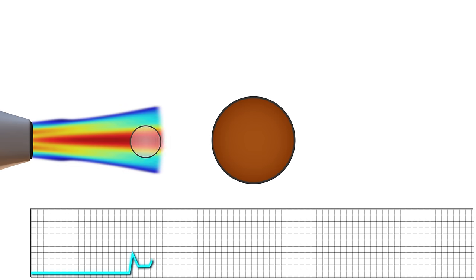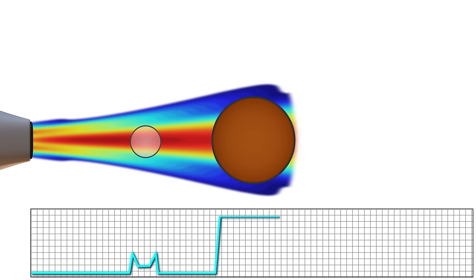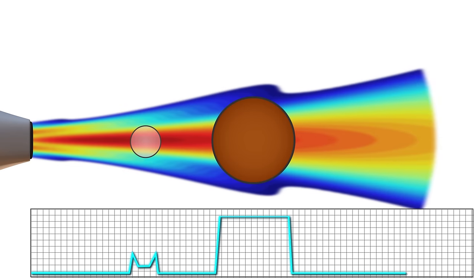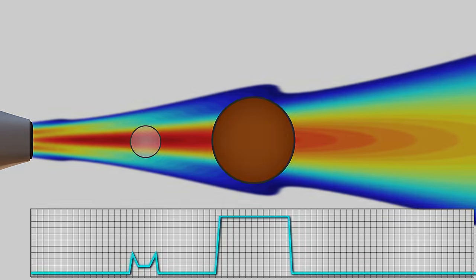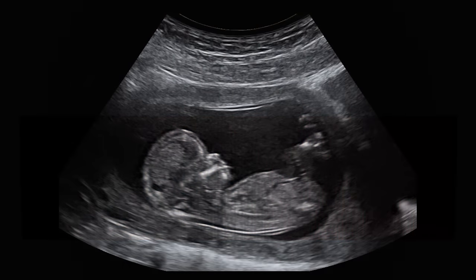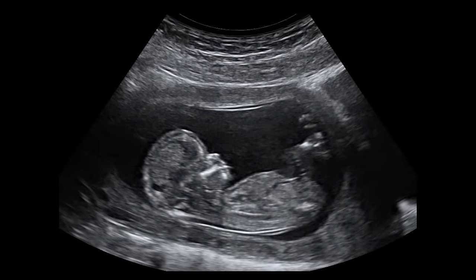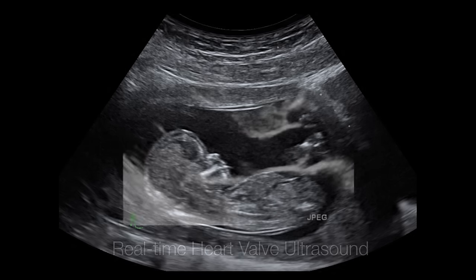Returning echoes are converted to electric signals, which a computer converts into points of brightness on the image, corresponding to the anatomic position and the strength of the reflecting echoes. A medical transducer contains a large array of crystals which allow it to make a series of image lines that, together, form a complete image frame called a sonogram.